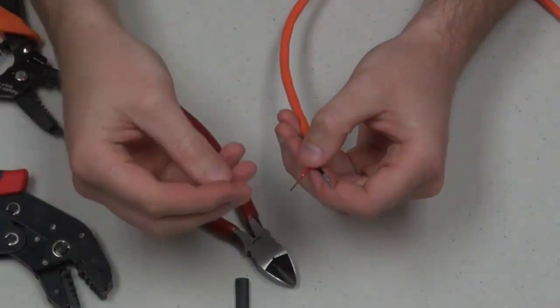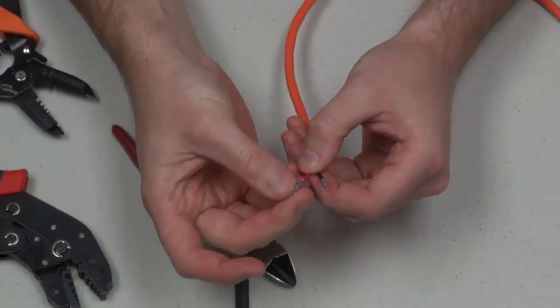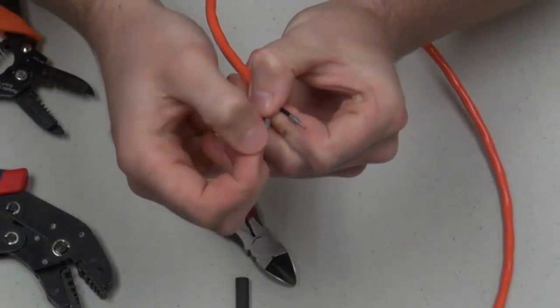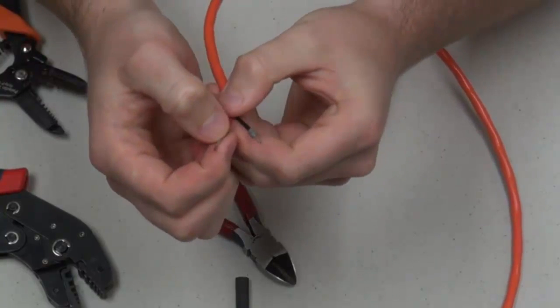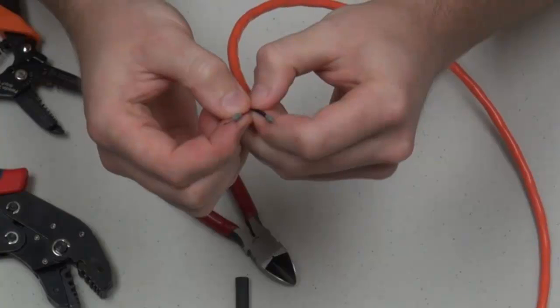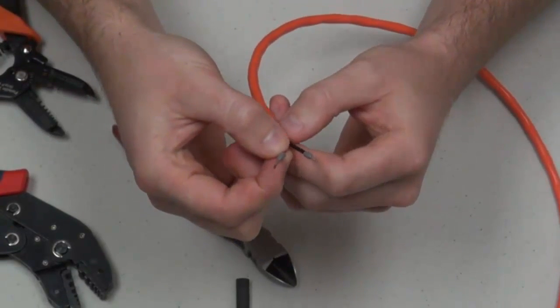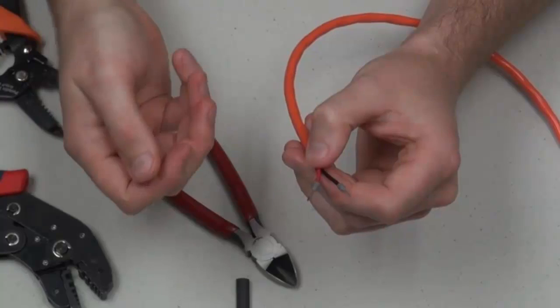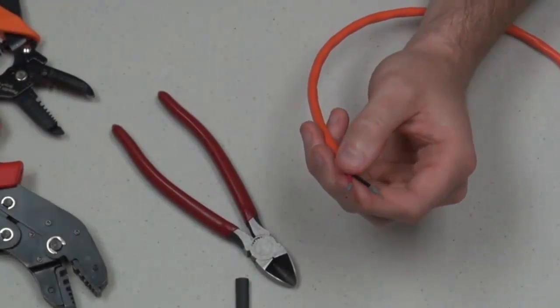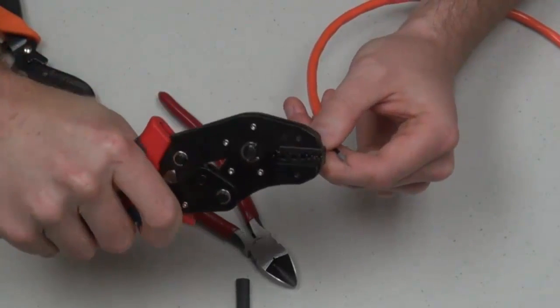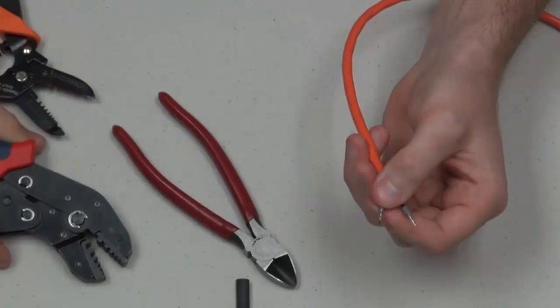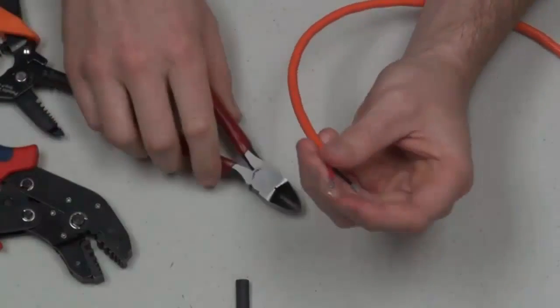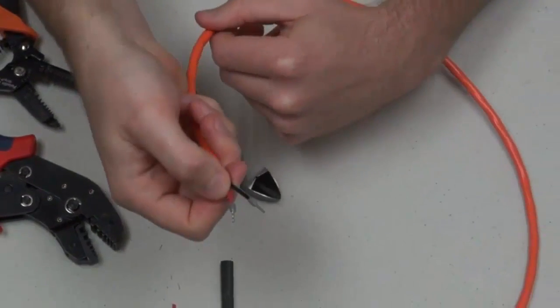Moving on to this red wire that I mentioned earlier. I made it a little bit long because I'm going to show you some here. But as you slide this ferrule down, you might be able to tell there's a little extra copper that comes out in the end. Generally, you don't want to see that happen just because it's going to make the installation a bit tougher for you in terms of landing these wires in their terminals. A lot of times these things are a little shallow. If you've got a bunch of wire hanging out in the end, you're going to end up bottoming out before you can get it all the way in there nicely. Not a big deal, though. Go ahead and crimp it just as you would. You hear the click. You can see the extra cable. And it's real simple. Just grab a couple of dikes here and snip off that extra copper.